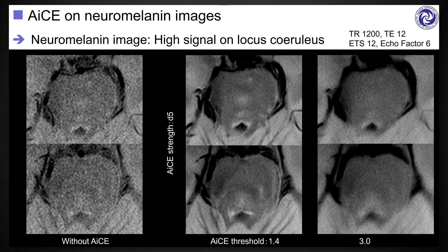Neuromelanin imaging is one of the challenging techniques to visualize neuromelanin in the locus coeruleus, which is a very small structure in the dorsal part of the pons. On the image without AICE noise reduction, a large amount of noise disturbs the small signal of the locus coeruleus. By selecting adequate AICE noise reduction, we can get a satisfactory image of the locus coeruleus. However, we have to be careful that if we select an inadequate threshold of AICE, the image would be blurred and visualization of the structure would be spoiled.